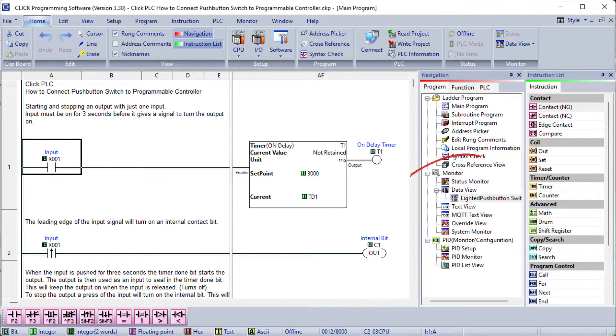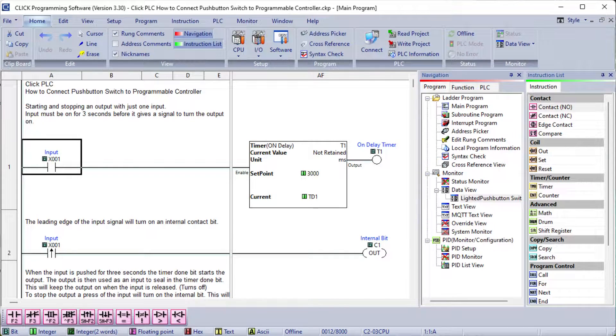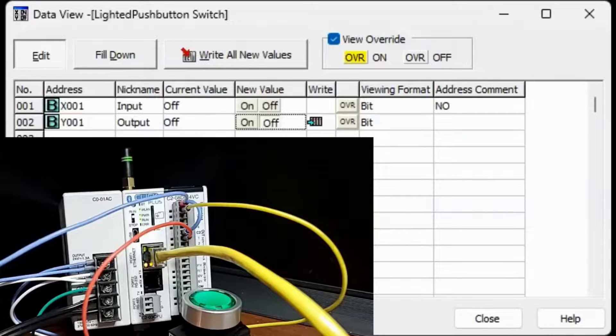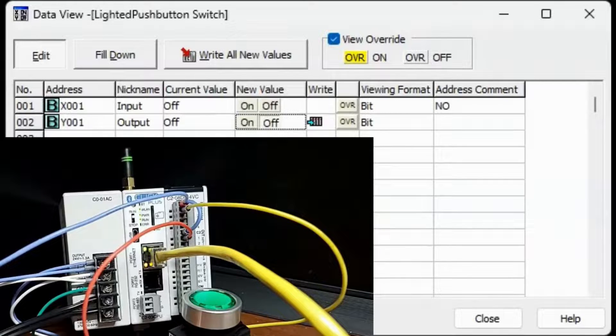We can quickly test our inputs and outputs of the Click PLC by using DataView in the Click programming software. Once connected online, the DataView can manually monitor or set the inputs and outputs before ladder logic programming is written.